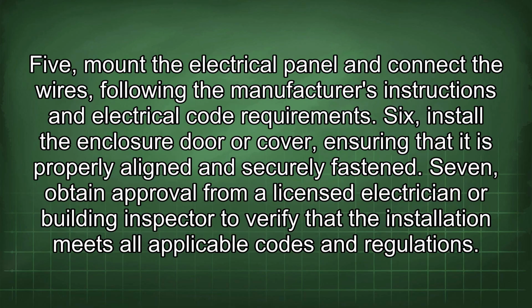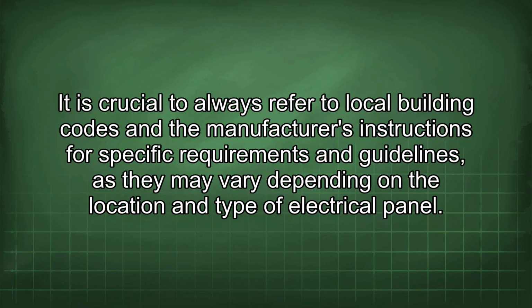5. Mount the electrical panel and connect the wires, following the manufacturer's instructions and electrical code requirements. 6. Install the enclosure door or cover, ensuring that it is properly aligned and securely fastened. 7. Obtain approval from a licensed electrician or building inspector to verify that the installation meets all applicable codes and regulations. It is crucial to always refer to local building codes and the manufacturer's instructions for specific requirements and guidelines, as they may vary depending on the location and type of electrical panel.